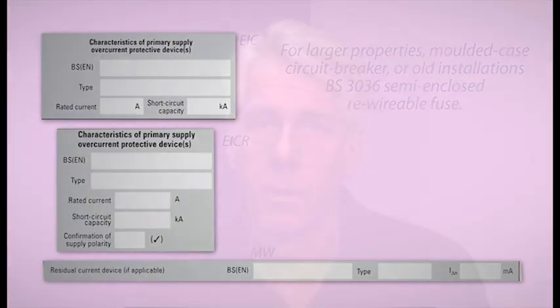For new installations, it should not be a problem determining the characteristic of the device, but for an EICR, it can often be difficult to ascertain, and in some situations will have to be an agreed limitation of the report. The next box says type. Now I've seen this filled in as "new one" or "grey one", but what it's actually referring to is the type of the characteristic of the device.